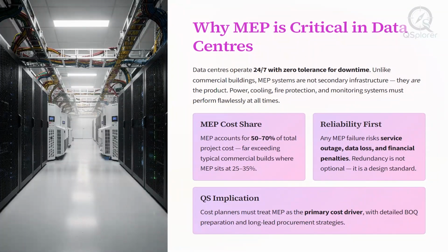When we think about a normal commercial building, we often consider the architectural structure as the main product, while MEP systems simply support it. But in a data center, the situation is completely different. The MEP systems are actually what keeps the facility operational. Servers generate an enormous amount of heat and require continuous cooling. They also require an uninterrupted power supply because even a few seconds of power loss can lead to service interruptions, data loss, and significant financial consequences. That is why redundancy is built into almost every major system.